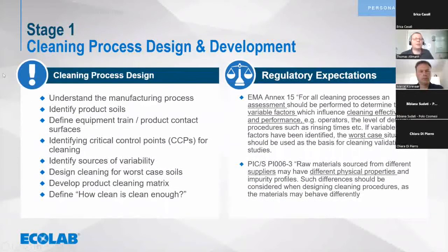The cleaning process design is, of course, to understand the manufacturing process, meaning what is the dirty hold time of a product. How long will the equipment stand dirty before I can start cleaning, because of a shift change or a public holiday when you are not working, or there could be several reasons. And is this dirty hold time at ambient temperature, or is the product maybe heated during filling, with a heat treatment on the surface for a certain amount of time?